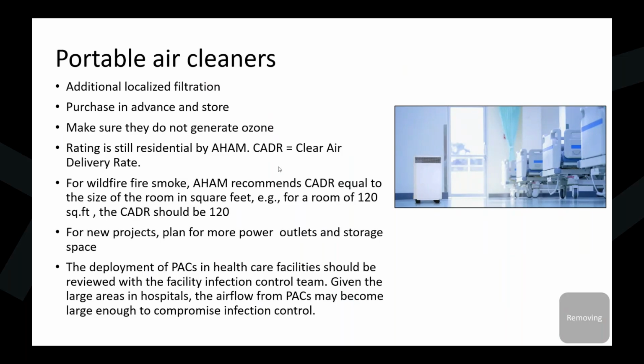They're still regulated by AHAM and use a metric called the CADR, the Clean Air Delivery Rate. Typically for wildfire smoke, AHAM recommends 1 CADR per 1 square foot of room. So basically, if you have a 120 square feet exam room, you will need to pick a portable air cleaner that's like 120 CADR. If you have a new project, we have recommended to some owners that you may need to have more power outlets in the areas where you can deploy portable air cleaners, and you need a place to store them. In any case, the deployment of PACs, especially in a healthcare setting, needs to be coordinated with infection control, especially in sensitive areas where there is a pressure requirement. You don't want your PAC to affect any code-required pressure requirement.